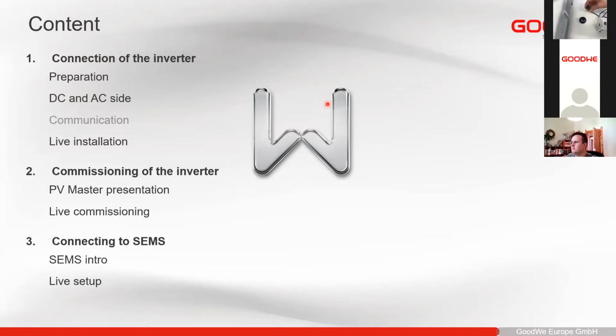And here is the connection also with RS485. You see here plus and minus, and here it's actually pre-wired with this adapter. And this adapter fits perfectly to the meter connection, this one that comes with the inverter. So you just plug it straight in there, and then it's connected to the inverter. Very easy. As I explained before, here you see the different CTs. So here you see that you have CT A, so it goes to phase 1. And here it also says house to grid with an arrow. So the arrow needs to point towards the grid. So if the grid is here on the right side, it needs to clamp on like this.